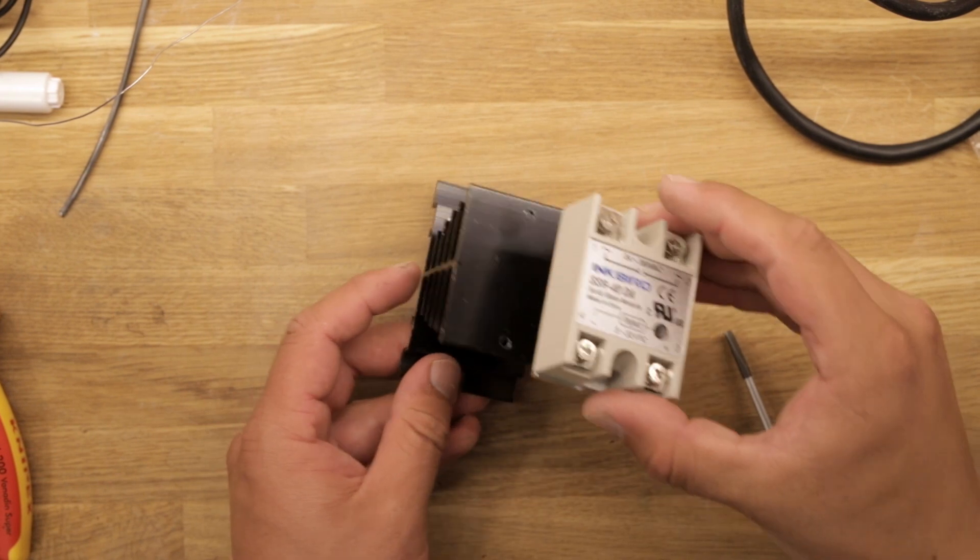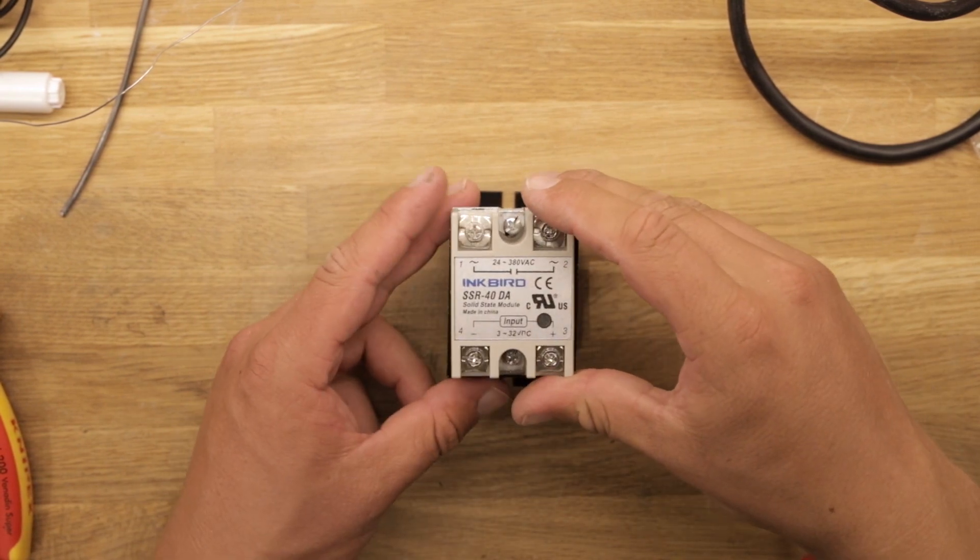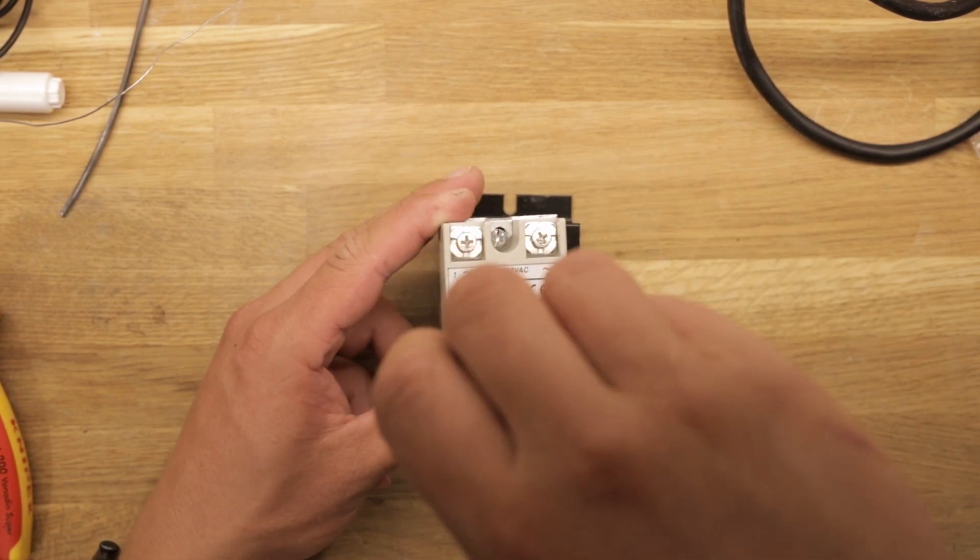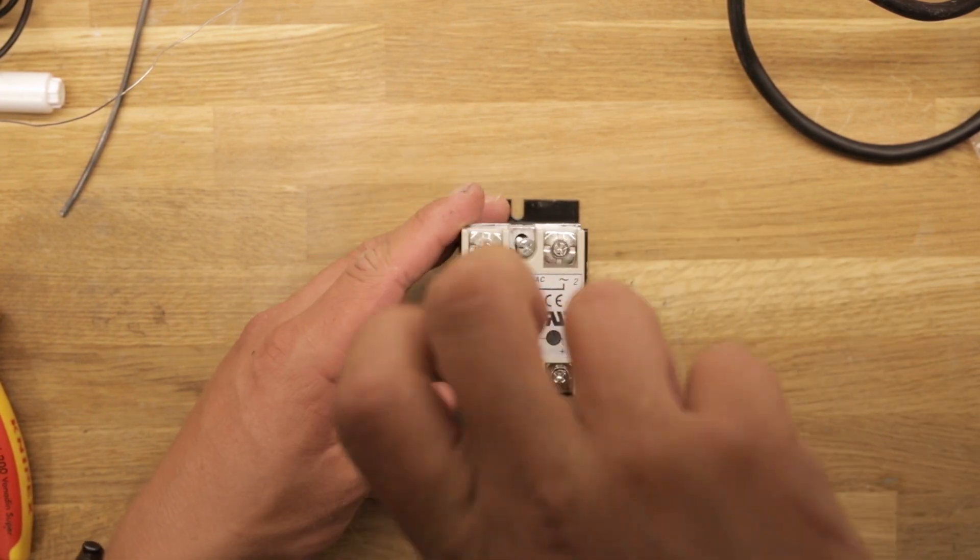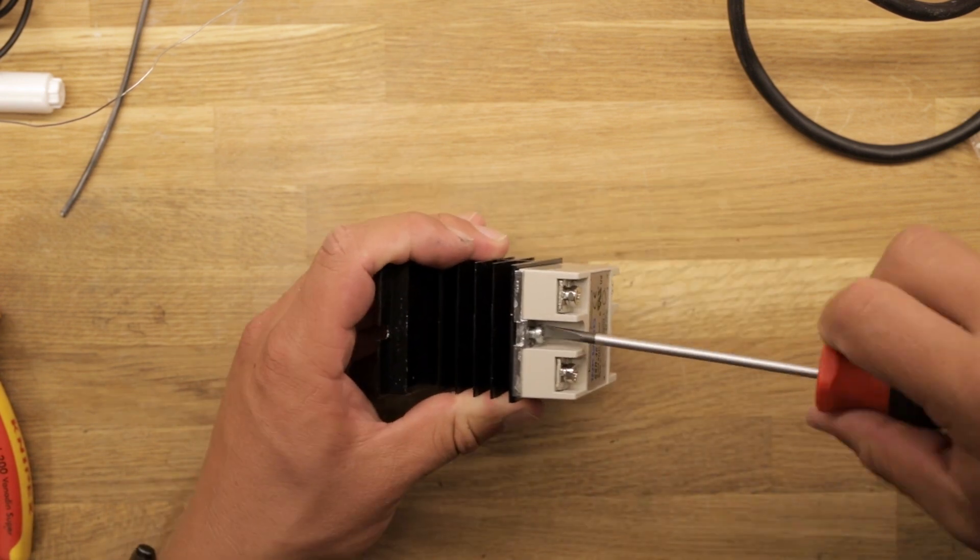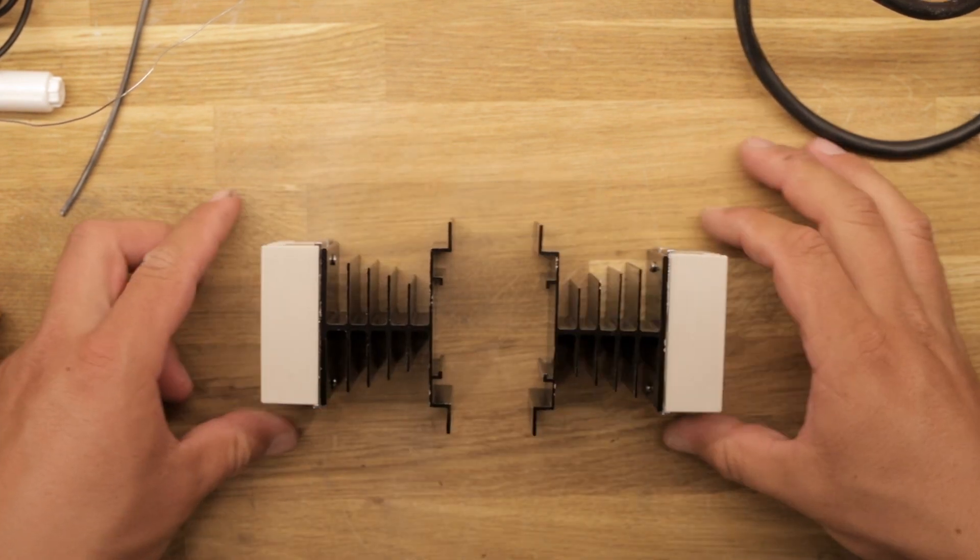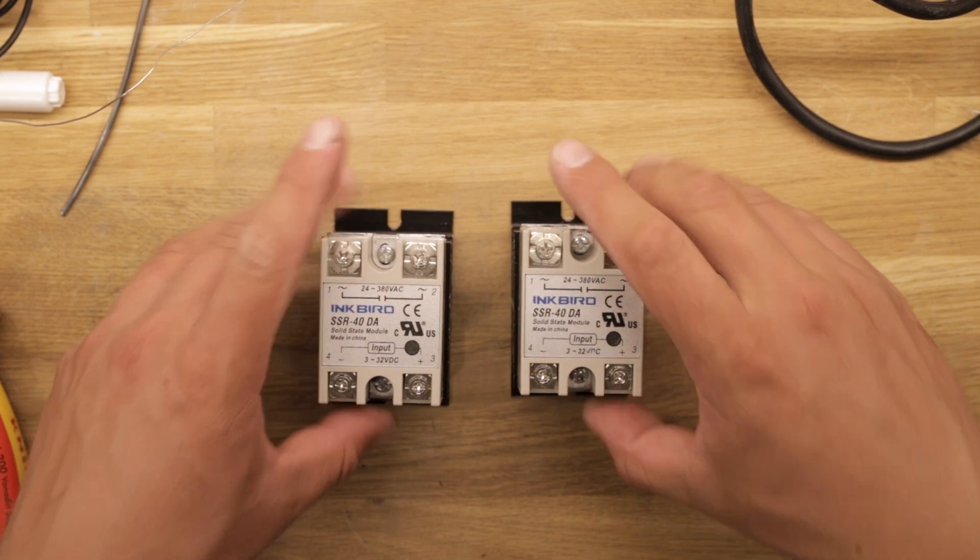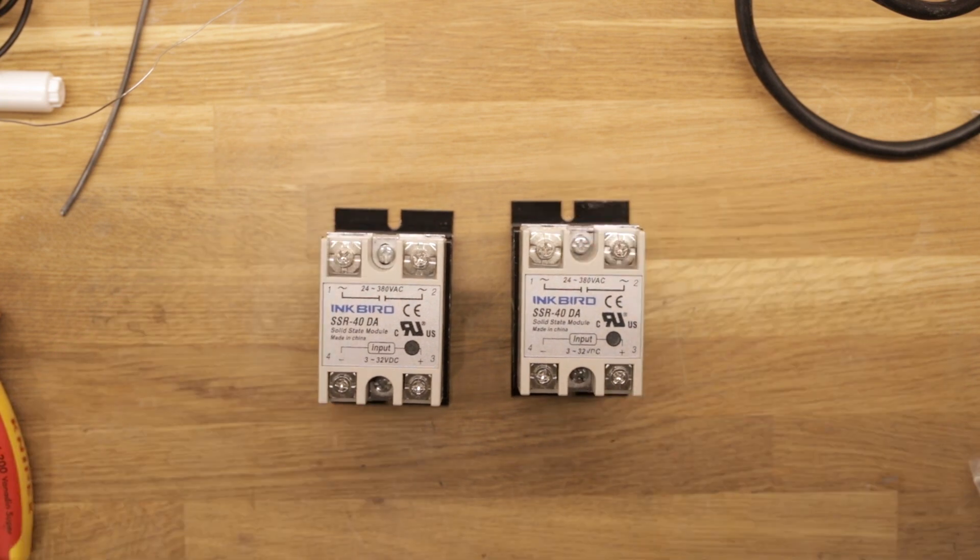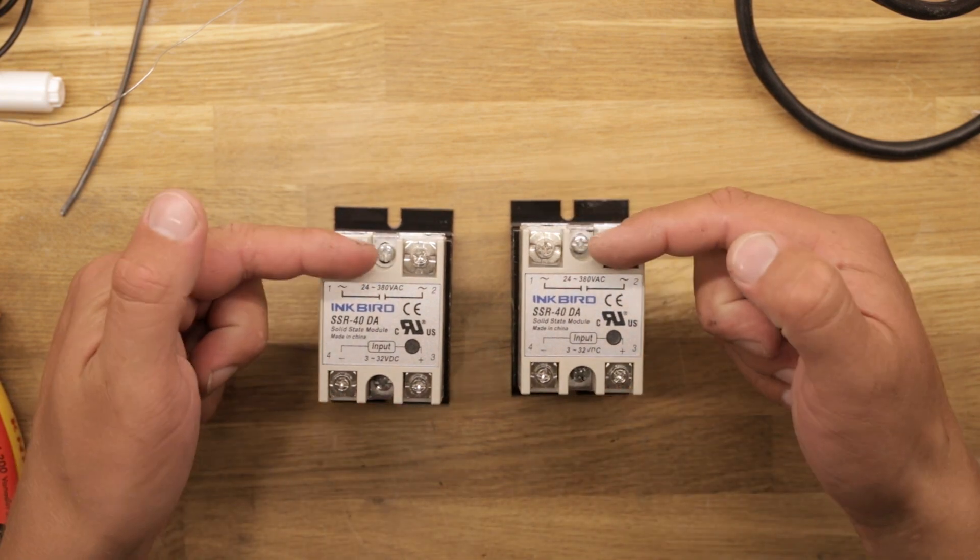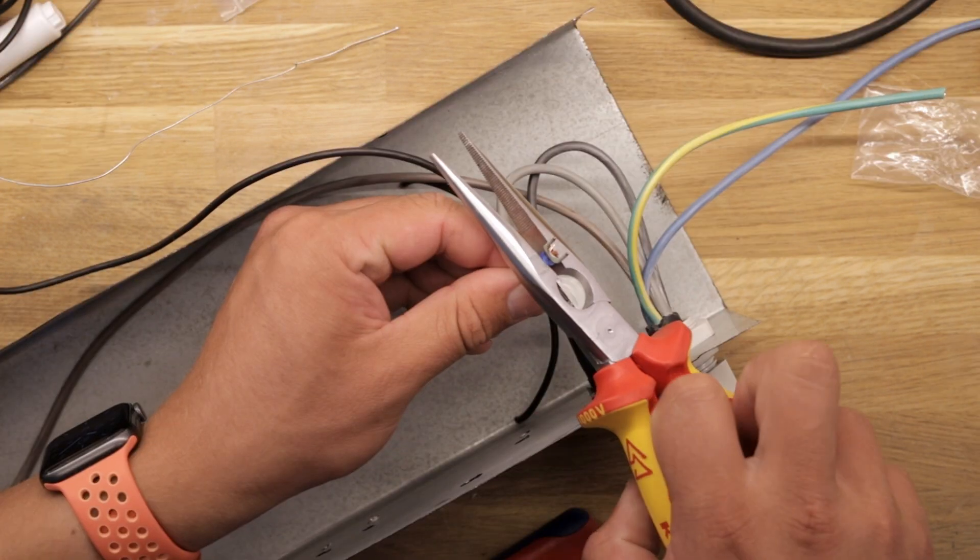Now we can move on to the solid state relays, which come with these oddly shaped heat sinks. They screw together, and ideally some heat sink paste should have been applied between the two surfaces. On these specific relays, pins 3 and 4 control the input, while pins 1 and 2 are the output connections for the high voltage side.